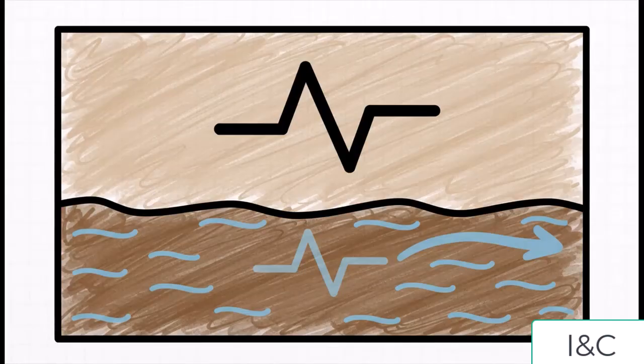So what's causing that drop? This is a super common effect, usually because of the water table. Deeper soil tends to be wetter, more saturated with water, and wet soil is a much better conductor of electricity, which means it has a lower resistivity. This test has basically found the water table for us.